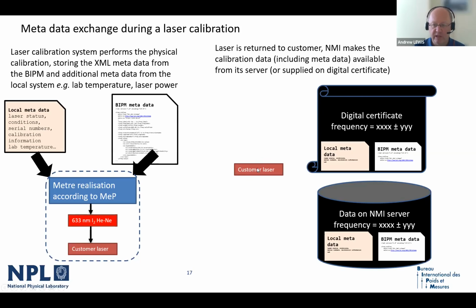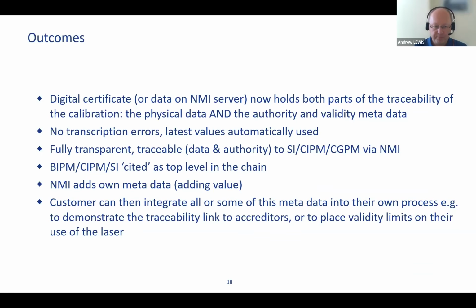When the laser is returned to the customer, the NMI makes the calibration data available either as a digital calibration certificate or as downloadable data from the NMI server. It doesn't just make available the frequency value plus the uncertainty, but it also offers this rich metadata format. That has several advantages. First of all, you have both parts of the traceability of the calibration. It has the physical data, the physical frequency of the laser, but it also has this authority and validity metadata, which is also important for quality aspects.